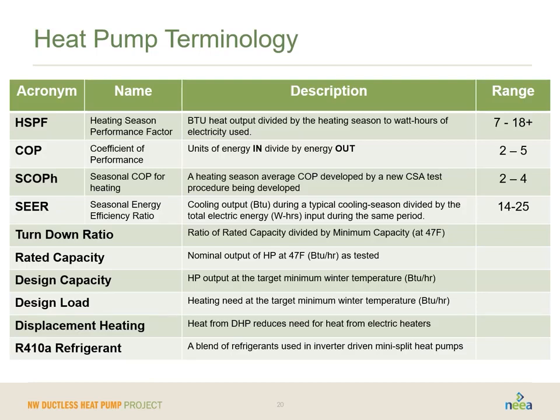The other couple things, I'm going to talk a lot about turn down ratio in a little bit, so let's skip over that and talk about design capacity and design load. Design capacity has to do with the ability, or the oomph, if you will, of the heat pump to produce heat at the winter design temperature for your home. The design load, on the other hand, is how much heat your house needs at the winter design temperature. If you do not produce as much as you need, you can imagine the house may not be very warm. So that's a critical element when we talk about sizing and design: getting the design capacity and the design load to match, or making sure that the entire system of the home, if it's a displacement system, so the combination of the ductless heat pump and the electric resistance heat, is capable of meeting the design load.